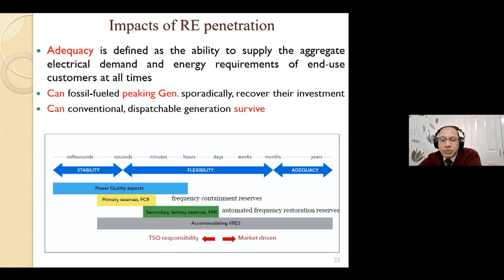The third parameter is actually the adequacy. We know during the peak time, especially overnight between 6 o'clock and 10 o'clock in the UK, we have a peak time, and we have to switch on some of the synchronous machines that can be switched on and off quickly, maybe within 10 to 15 minutes maximum, to cater for the peak load. With the integration of renewables, in addition to storage, the synchronous machines used for peaking the loads will not be able to recover their investment. So there is a threat for the existing synchronous machines at the moment from including renewable energy during peak time in this case.